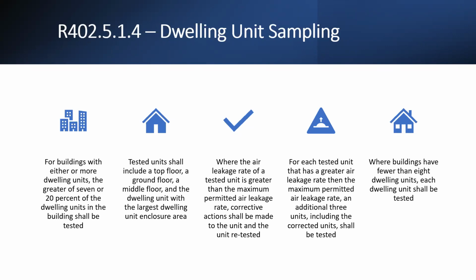So before, if you were 4 stories or higher, you were commercial and there was a sampling protocol, but if you're 3 stories or less, then you're considered residential, and there was not a sampling protocol. So there was some confusion: the city would allow sampling, but it wasn't really in the residential allowances. But now they've brought this from commercial directly into residential to allow for a sampling protocol. That does include both blower door and duct blaster testing.